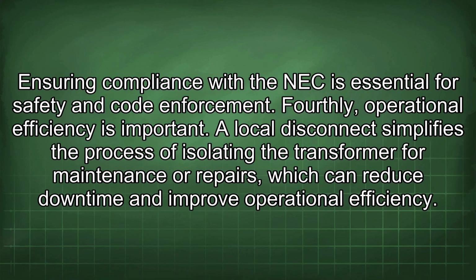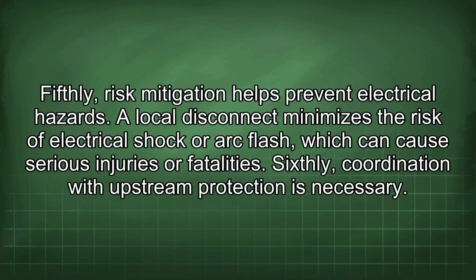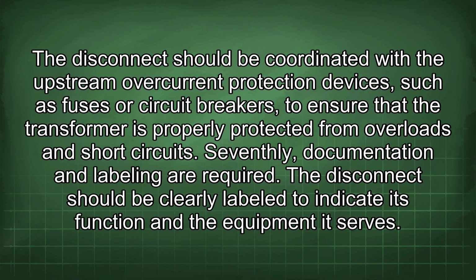Fourthly, operational efficiency is important. A local disconnect simplifies the process of isolating the transformer for maintenance or repairs, which can reduce downtime and improve operational efficiency. Fifthly, risk mitigation helps prevent electrical hazards. A local disconnect minimizes the risk of electrical shock or arc flash, which can cause serious injuries or fatalities. Sixthly, coordination with upstream protection is necessary. The disconnect should be coordinated with the upstream overcurrent protection devices, such as fuses or circuit breakers, to ensure that the transformer is properly protected from overloads and short circuits.